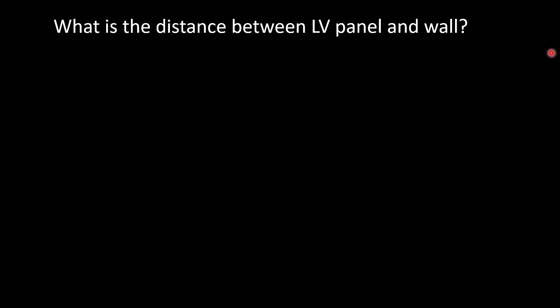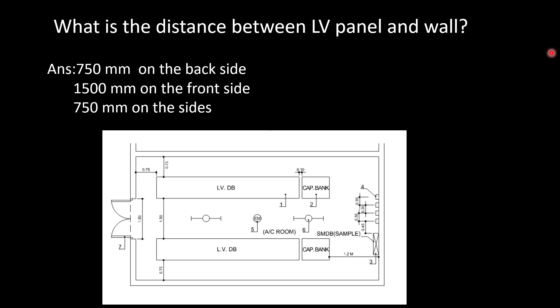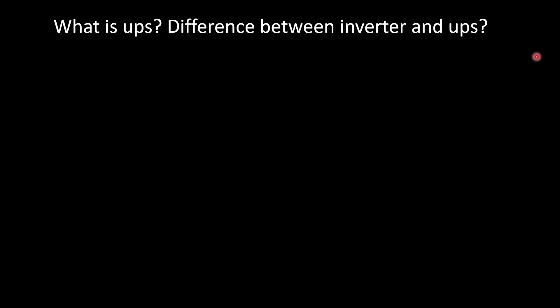What is the distance between an LV panel and the wall? This is predominantly asked in GCC interview questions. The answer: minimum clearance shall be 750 mm on the back side, 1500 mm (1.5 meters) on the front side, and 750 mm on the sides. As per DEWA regulations: back side 0.75 m, side 0.75 m, front side 1.5 m. The minimum distance between an LV panel and a capacitor bank is 100 mm.